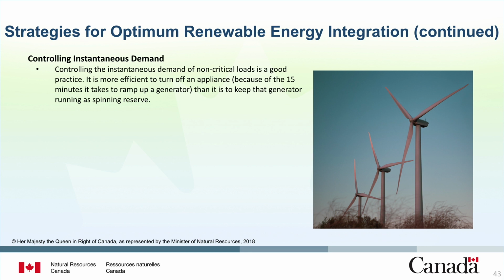To continue, here are 3 more strategies to optimize intermittent renewable energy generation on an existing utility grid. Controlling the instantaneous demand of non-critical loads is a good practice. It is less wasteful to turn off an appliance for the 15 minutes that it takes to ramp up a generator than it is to keep that generator running as spinning reserve.